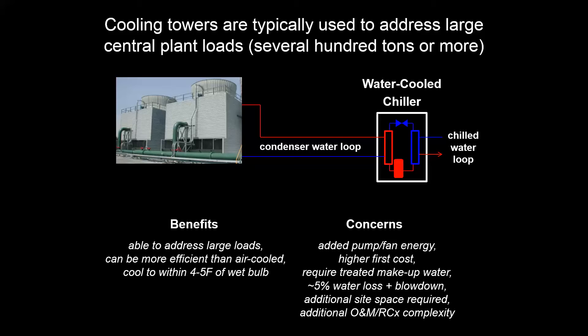There's make-up water, which if you're in a drier environment can be an issue. You have water loss and blow down, and you need controls to be able to house these things, plus some additional maintenance. But when you consider how much water is used at a power plant, it's important to consider the balance between a little more water used on site with some electrical savings, versus water used at the power plant to generate that electricity. In the context of RCX, with this extra equipment and these extra loops, you have extra complexity and more things that can go wrong — more to look at with the cooling tower, make-up water, leaks, and how you run those fans.